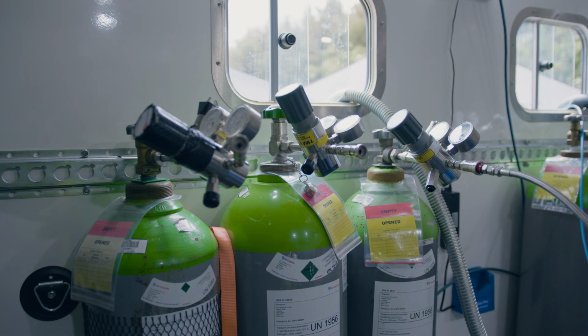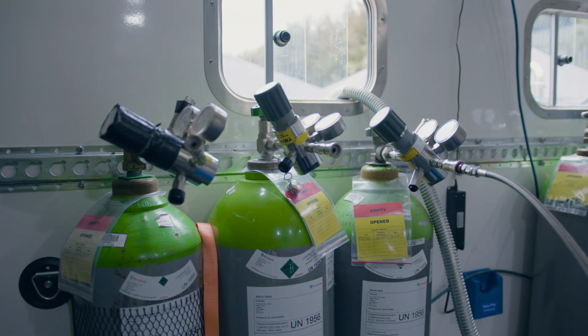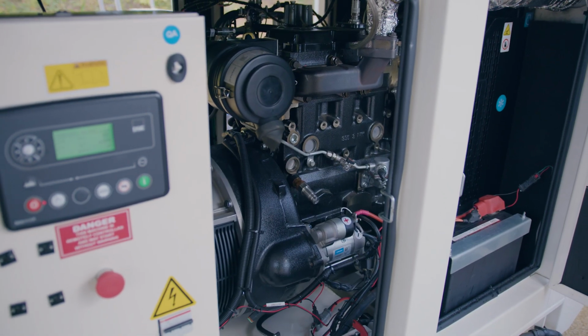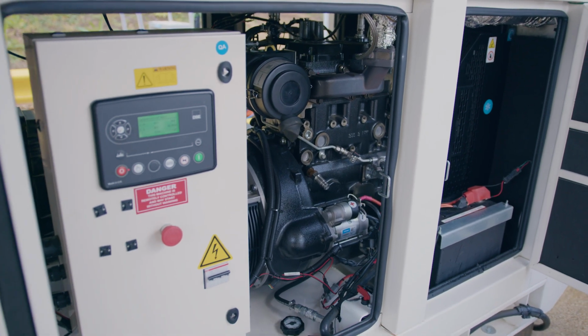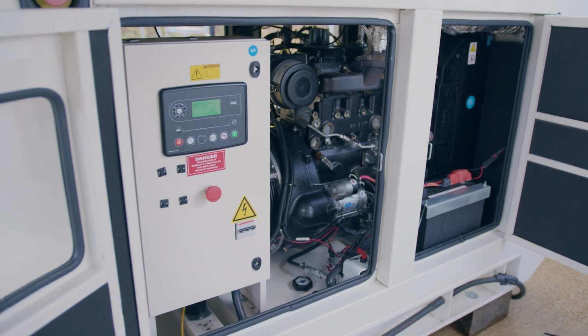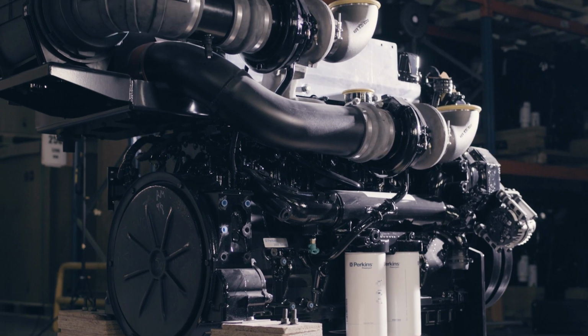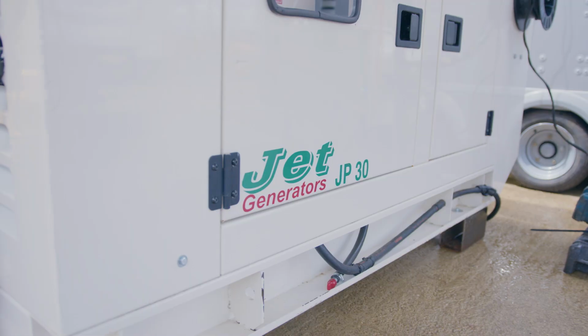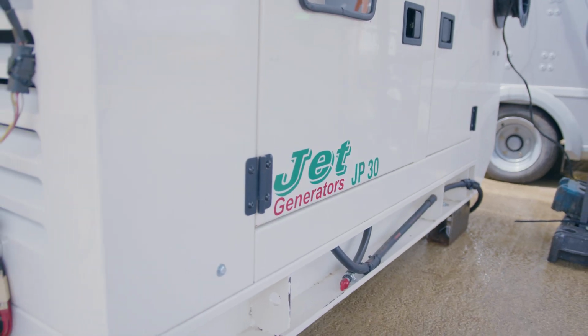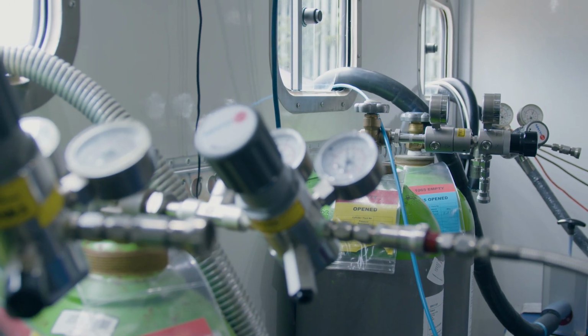What we have found is that this is a one-to-one replacement for diesel, both in a pure fashion and in a blended form - 100% diesel, 50%, 80%, with the same equipment, the same fuel injection equipment on the engine. There's no cleaning of tanks needed, no filters needed changing ahead of moving back to HVO. So it makes it very flexible and really allows customers to have peace of mind that they can keep running and not have to worry about things if there's a lack in supply and a gap in being able to source the fuel.